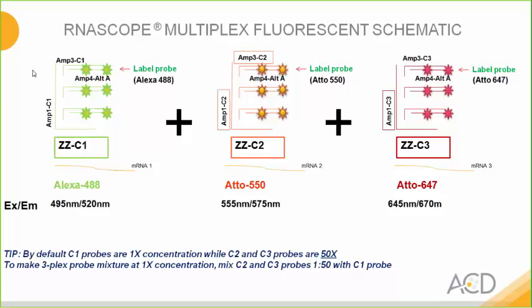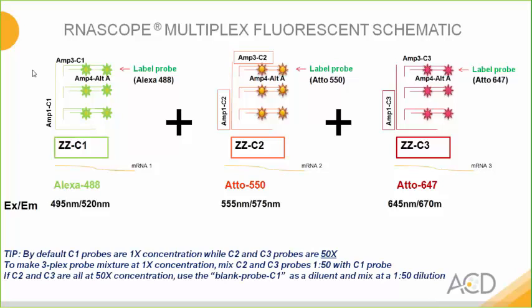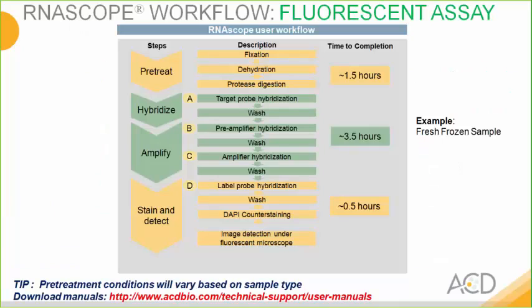Thus, in order to plex, say for example, if you want to detect 3 targets at the same time, you would mix the C2 and the C3 probe in the C1 probe in the ratio of 1:1:50. If, for example, you have targets that are not in the C1 probe, they are in the C2 and/or the C3 probe, that's no problem at all, because we do provide a probe diluent which you can then use to make your probe mix and use accordingly.